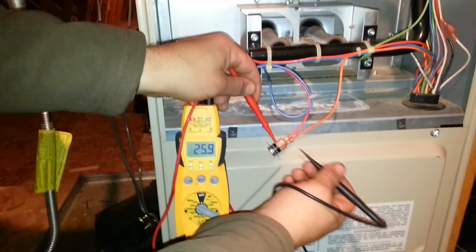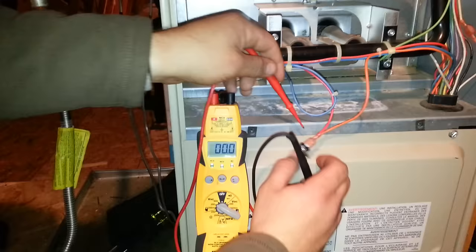But it will also allow you to check it — trip it again and check it the same way. Zero on that side, 24 volts across it, 24 on that side. So that one's tripped, you can tell.